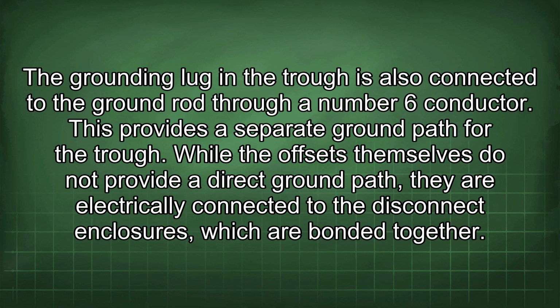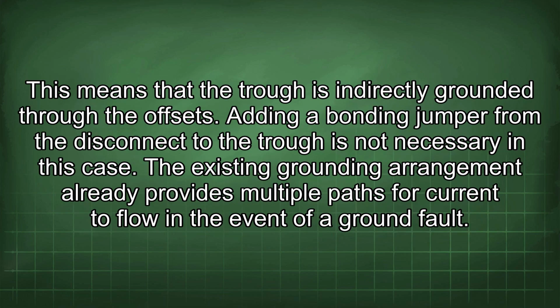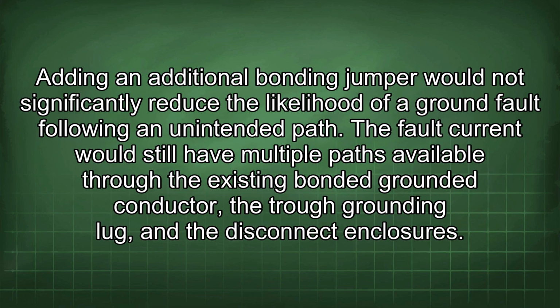While the offsets themselves do not provide a direct ground path, they are electrically connected to the disconnect enclosures, which are bonded together. This means that the trough is indirectly grounded through the offsets. Adding a bonding jumper from the disconnect to the trough is not necessary in this case. The existing grounding arrangement already provides multiple paths for current to flow in the event of a ground fault. Adding an additional bonding jumper would not significantly reduce the likelihood of a ground fault following an unintended path.